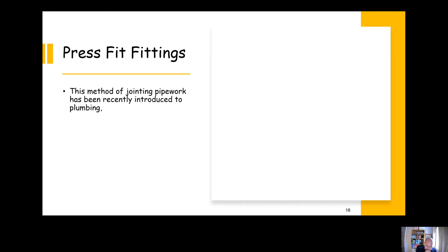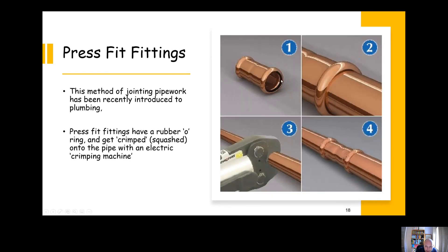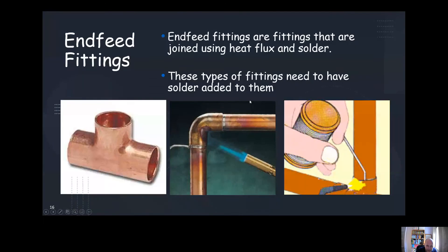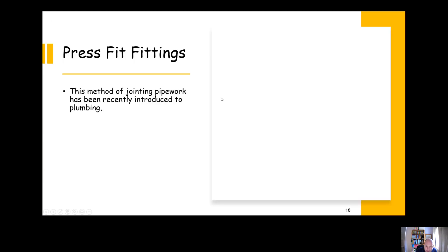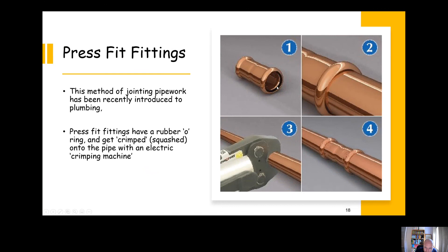Press fittings are a slightly more recent introduction to plumbing. They have a rubber o-ring inside and they look a little bit like integral solder ring fittings. You can see a rubber o-ring there instead of a solder ring. What happens is you get a crimping machine which would crimp the rubber o-ring tightly onto the fitting, squashes it onto the fitting, and that keeps it sealed. That's a heat-free method of jointing. Some sites don't allow hot works, which is working with blowtorches, and in that case we might use press fit fittings.